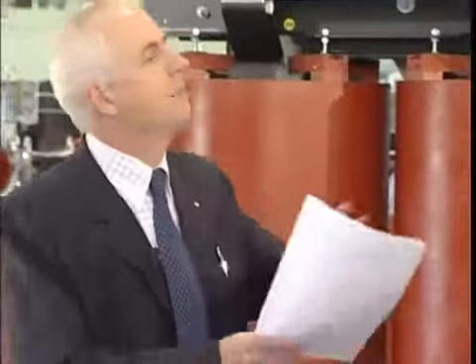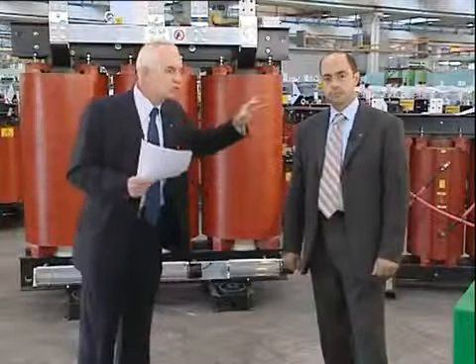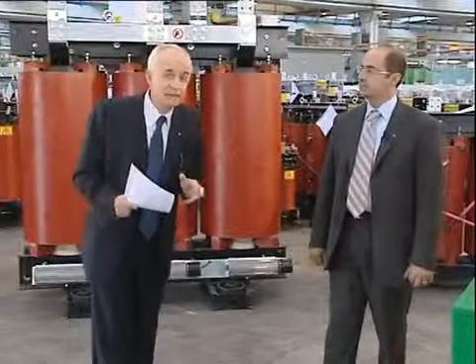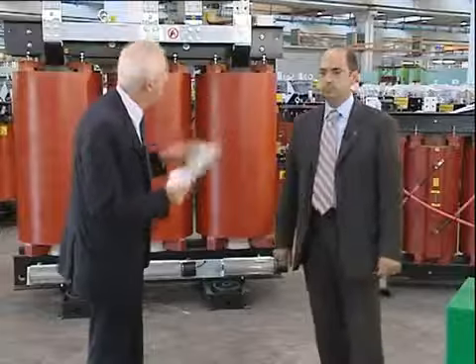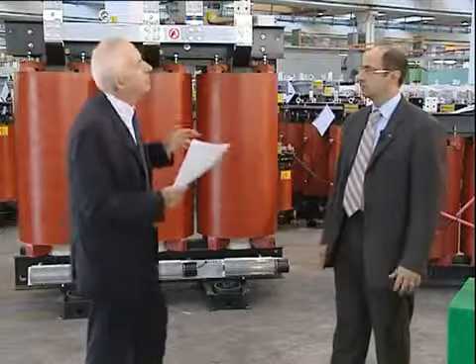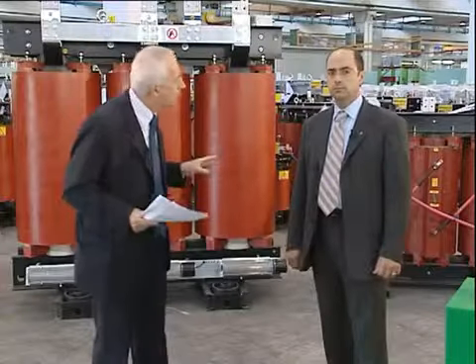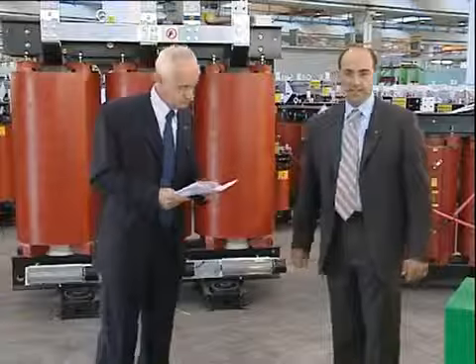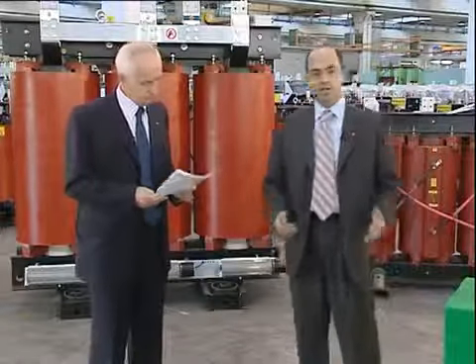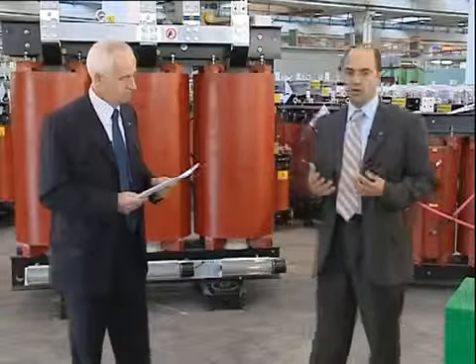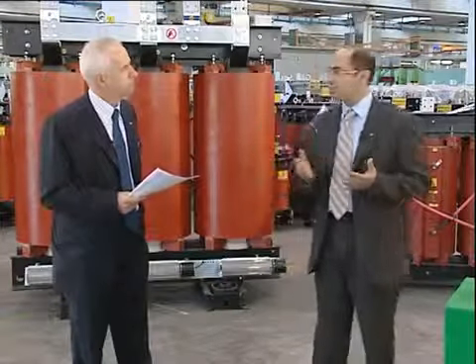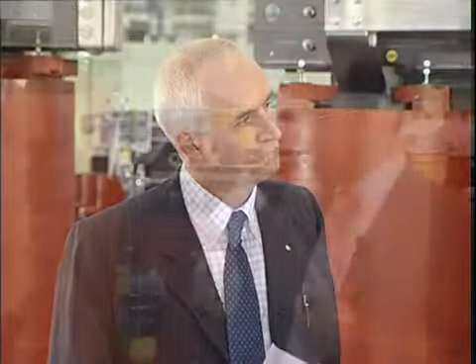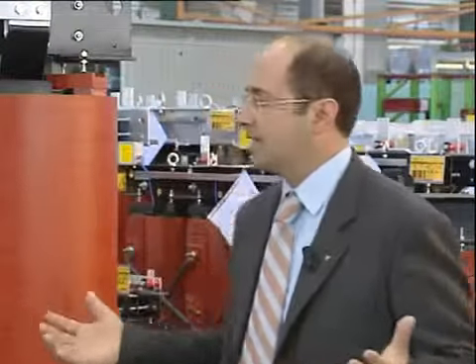If you allow me, I have prepared a whole series of questions, and I would therefore like to immediately get to the point. The first question pops up spontaneously. Here we can see a series of resin-insulated low-medium voltage transformers. Why aren't there any oil-insulated transformers? Or rather, in the past, EDM produced oil-insulated transformers, while now it no longer does. Why is that? We stopped manufacturing that type of transformer several years ago because oil-insulated transformers imply higher installation and maintenance costs. Moreover, they are less safe than resin-insulated ones. We aim at manufacturing high-quality and extremely safe products, and, as a consequence, we inevitably chose to produce resin-insulated transformers.